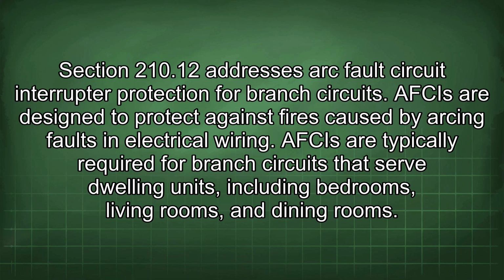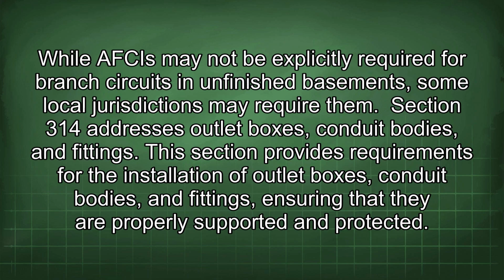Section 210.12 addresses arc fault circuit interrupter protection for branch circuits. AFCIs are designed to protect against fires caused by arcing faults in electrical wiring. AFCIs are typically required for branch circuits that serve dwelling units, including bedrooms, living rooms, and dining rooms. While AFCIs may not be explicitly required for branch circuits in unfinished basements, some local jurisdictions may require them.